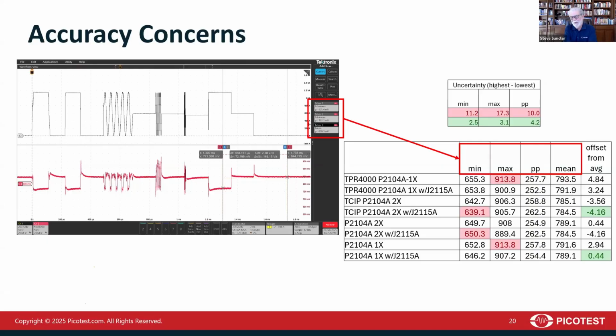And when we did the statistics of the minimum and maximum and peak to peak voltages and the mean voltages, we ended up with significant differences. In fact, the difference in maximum excursion voltage was 17.3 millivolts. In peak to peak, it was 10 millivolts. And for the minimum, it was 11 millivolts. And this is really problematic because we took different probes, measured on the same demo point with the same demo board on the same pads using the same channel of the same oscilloscope, and ended up with 17 millivolts of uncertainty. And for the purposes of our discussion, that's almost a third of our total allowable window. And that doesn't even include the tolerance errors yet of the scope channel to channel or scope to scope errors.